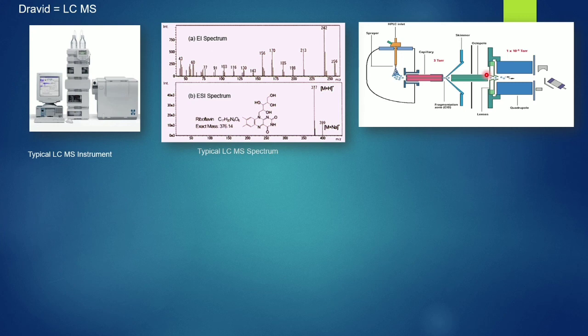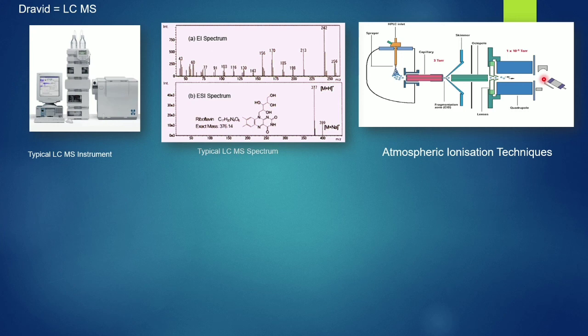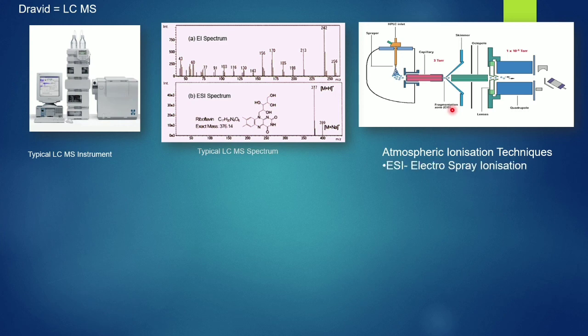After reaching there, if it gets the opposite charge again it will repel, and it will move through this quadrupole based on charge switching. The mass ions will be separated through this quadrupole and will reach the detector. This is why we say that only ionized compounds will be detected in LCMS — because they must have a charge. If there is no charge it will not move through the quadrupole; it will go to the atmosphere, to waste.